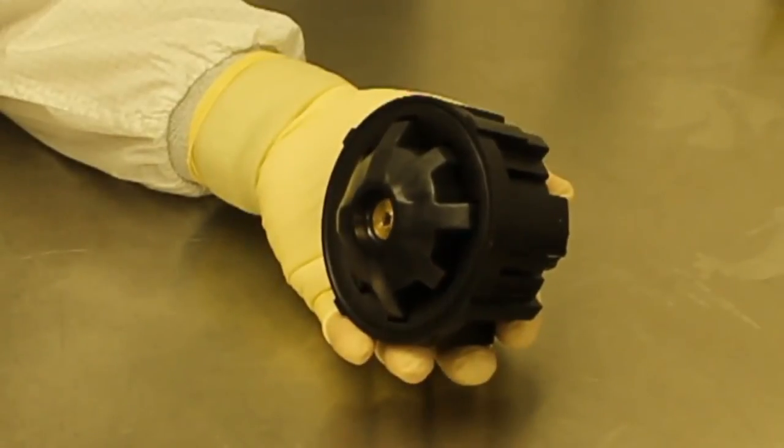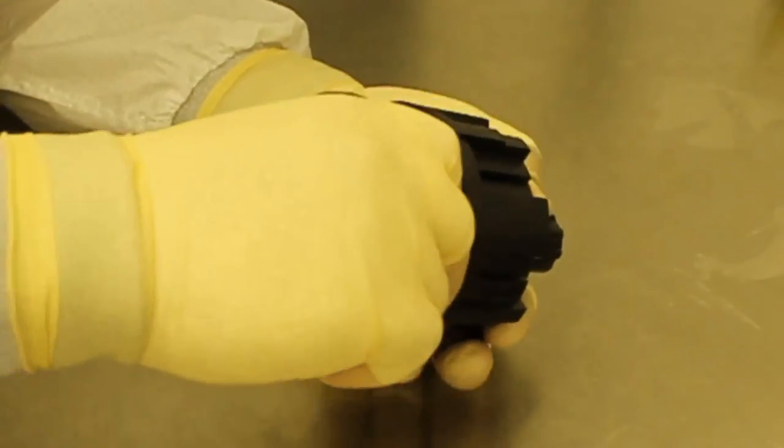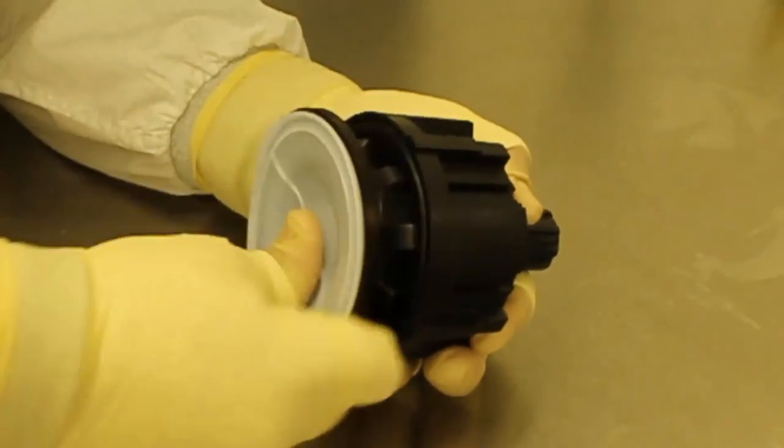Take the new diaphragm and ensuring the compressor is aligned as previously described, screw on the diaphragm until hand tight. Then, back it off one quarter turn.